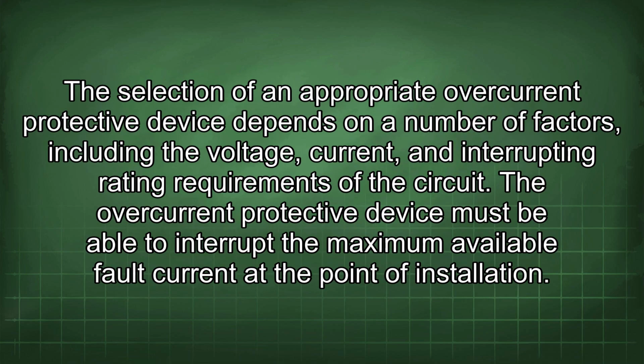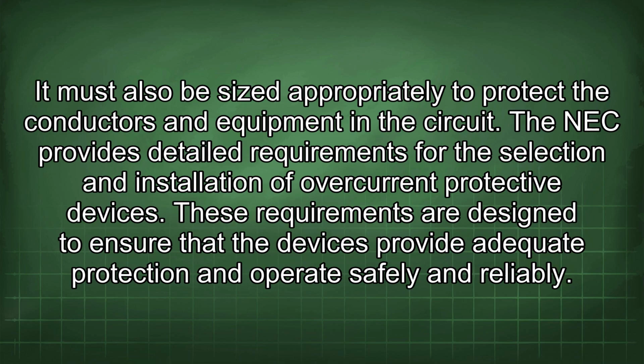The selection of an appropriate overcurrent protective device depends on a number of factors, including the voltage, current, and interrupting rating requirements of the circuit. The overcurrent protective device must be able to interrupt the maximum available fault current at the point of installation. It must also be sized appropriately to protect the conductors and equipment in the circuit. The NEC provides detailed requirements for the selection and installation of overcurrent protective devices. These requirements are designed to ensure that the devices provide adequate protection and operate safely and reliably.